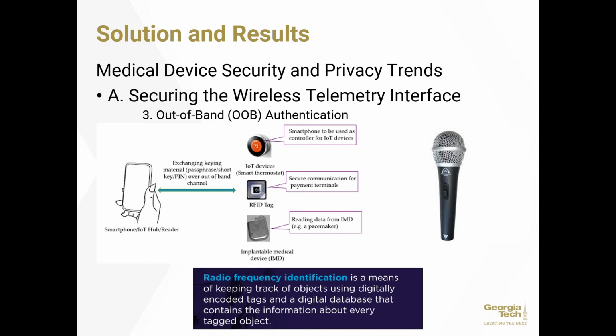The patient is alerted when a key exchange occurs through vibrations produced by a piezo element connected to the RFID device. The programmer, at a distance of no more than 0.6 to 0.9 meters, listens for the key and then establishes a secure authenticated channel with the IMD.